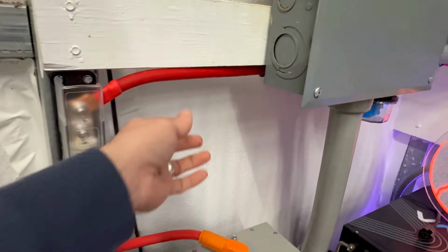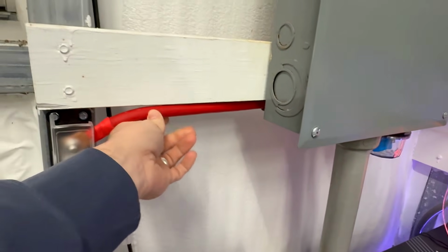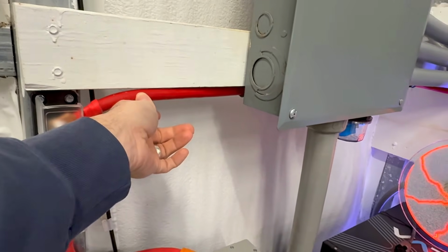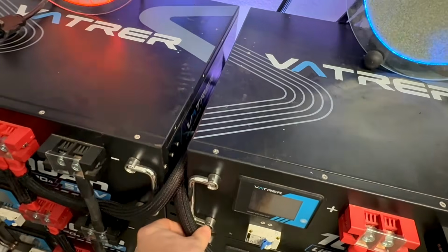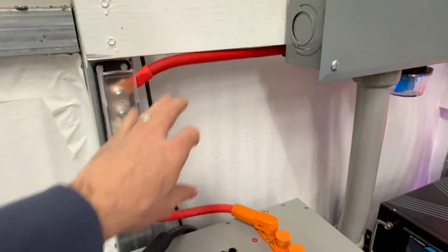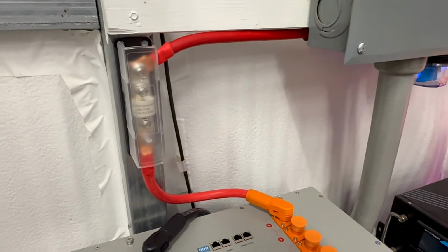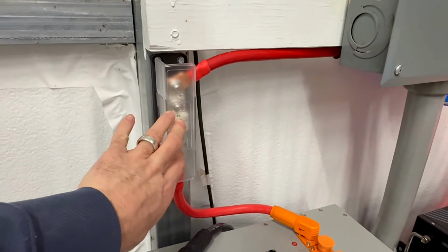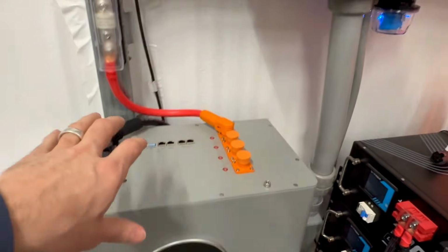They probably could go a little smaller on the fuse, but 225 is fine. Now, as you can see, I'm not using conduit. You should use conduit—that's something I'd recommend doing. I do use sleeves for my cables; it's currently not on this, but it will be installed in the future.